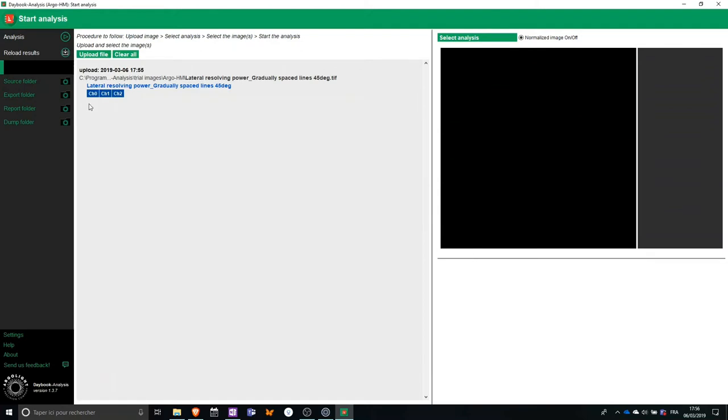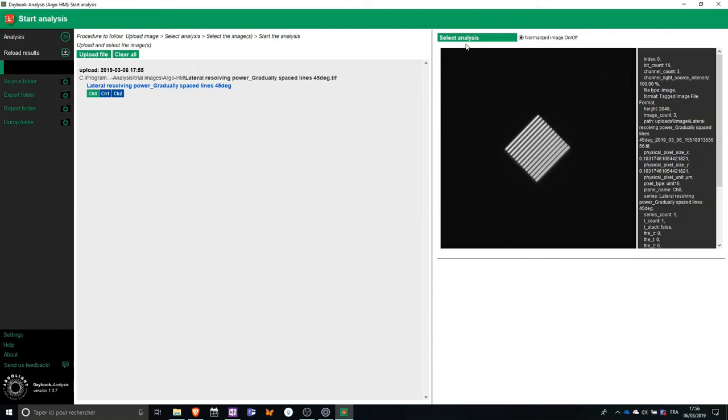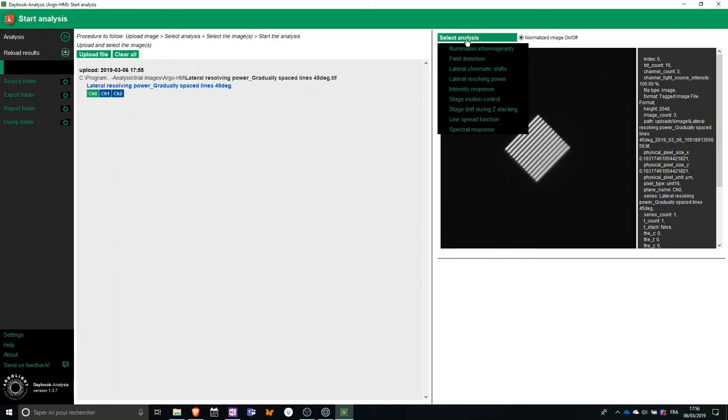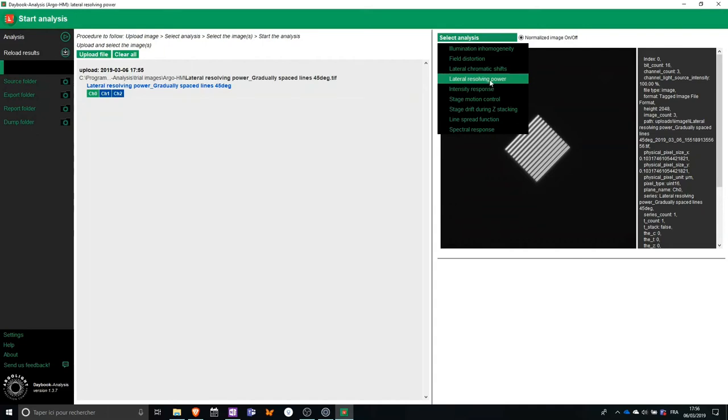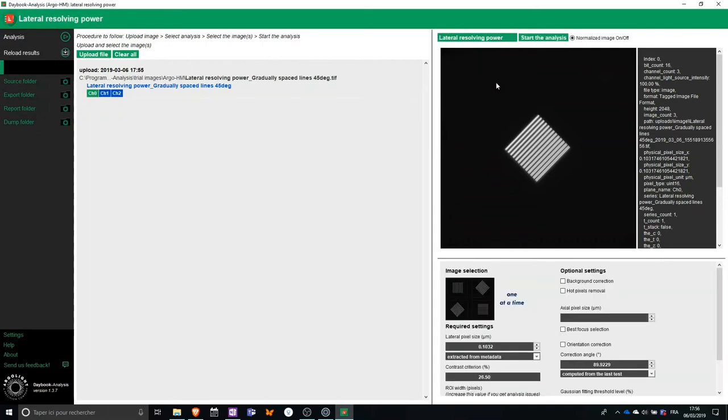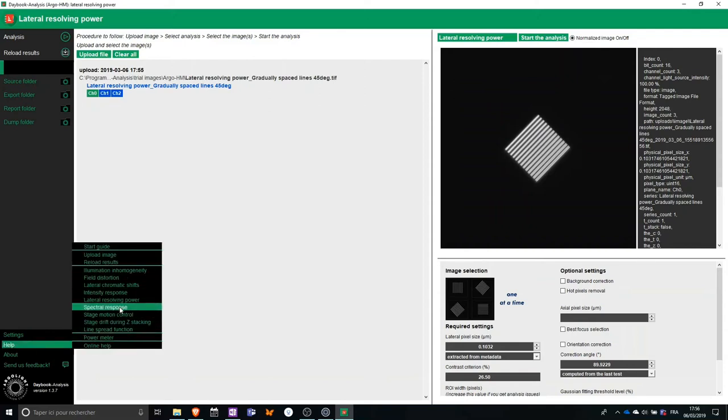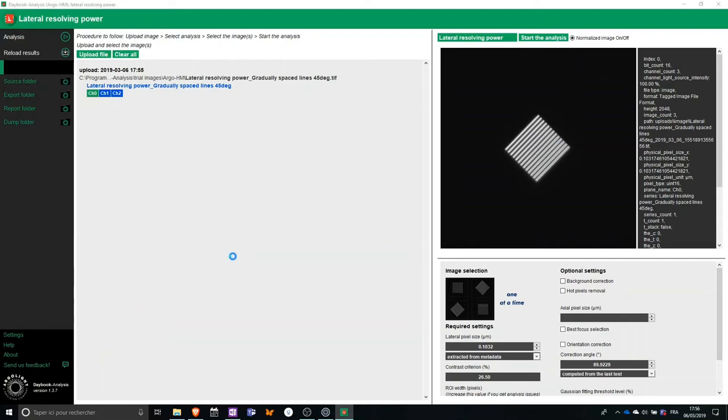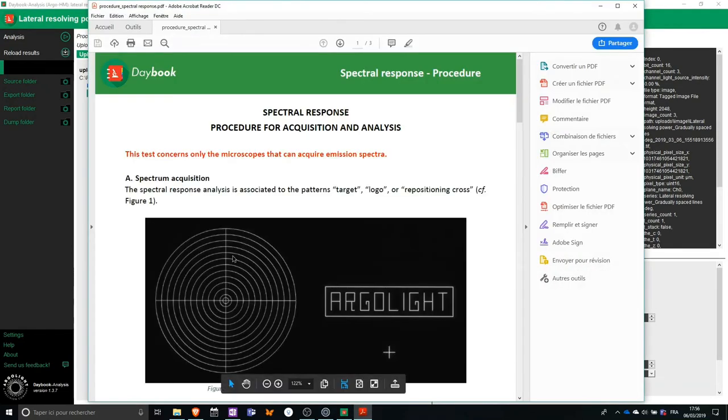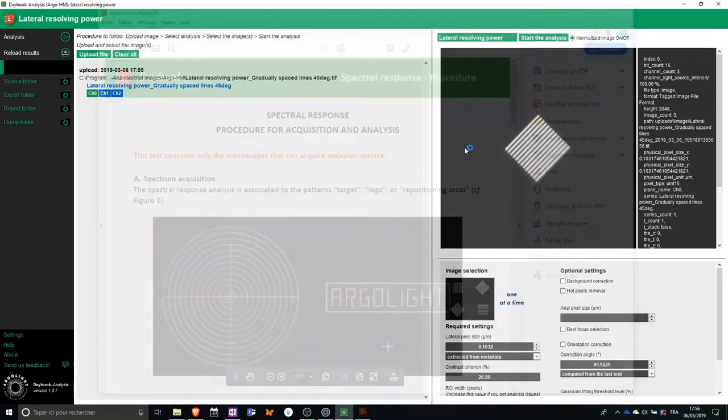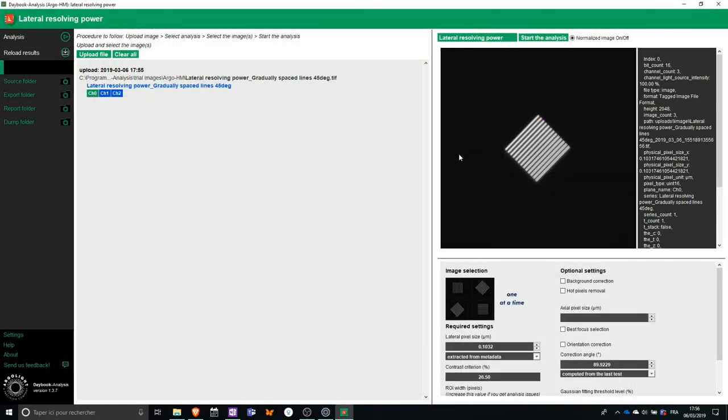Once I have my image, I can select the type of analysis I want to perform. Today, I want to perform lateral resolving power. Each of these analyses requires a specific type of image. If I don't know what type of image I need, I can go to Help, select the name of the test, and I will get an easy to read PDF that explains to me what type of image I should take and how to process them.